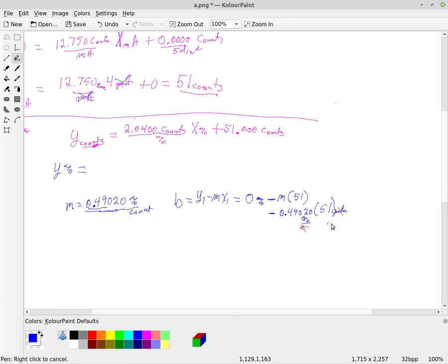Okay, so that's going to be 25, and since this is a scaling equation, it's going to have 3 extra zeros to give me 5 digits, and the unit for that is percent. So the top one up here in this magenta color is going from percent to counts.